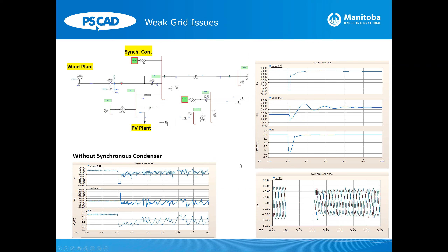When I mentioned earlier that networks have resonance and their characteristics play a critical role, in software like EMT we're able to capture the impedance of the network. So the network impedance plays an extremely important role when we're looking at performing these studies. Say, for example, you have a wind farm and you want to connect to your system, and this wind farm injects or absorbs this high frequency parallel resonance. If this parallel resonance enters the control systems of the wind farm, and it in turn amplifies this parallel resonance, it can cause problems. So it's very important to look at the network resonance before connecting your wind farm, and perform studies to see whether these resonances play a role in the operation of the wind farm or HVDC.